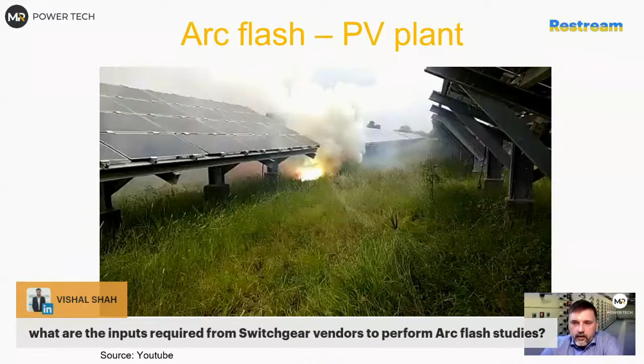So, question from Hannah: Is there a piece of equipment or a stage along the power flow infrastructure which is more likely to be affected by arc flash? I would say, if you would like to consider something as a high probability of arc flash to happen, aside from activities of people, the high probability would be always anything which is exposed. So if you have any bus bar going outside of your transformer, or badly maintained equipment like old equipment, it is highly likely that something can happen.